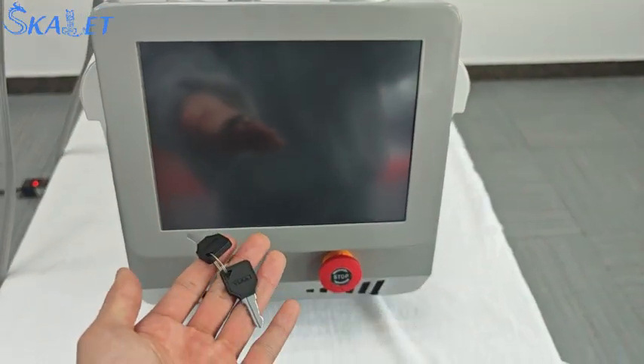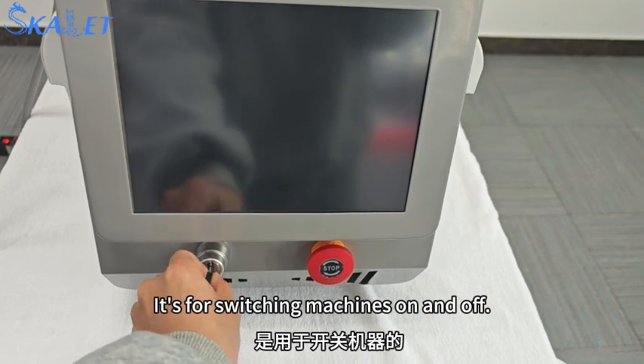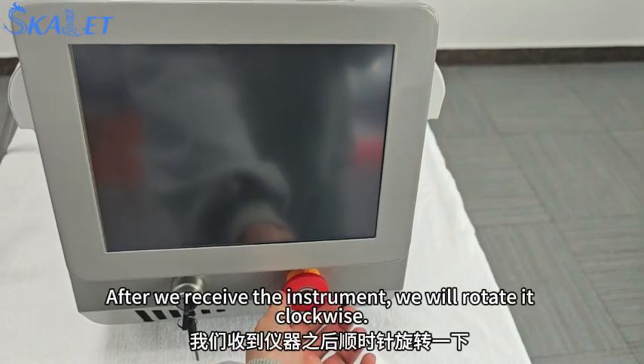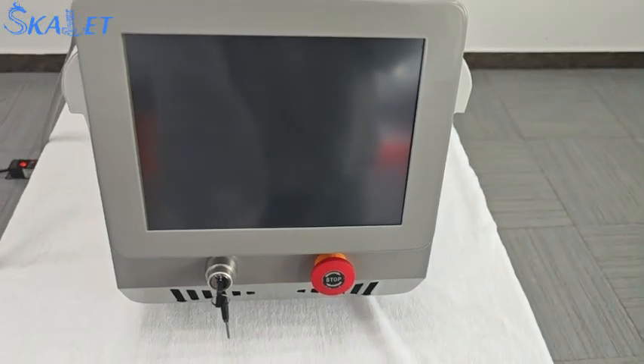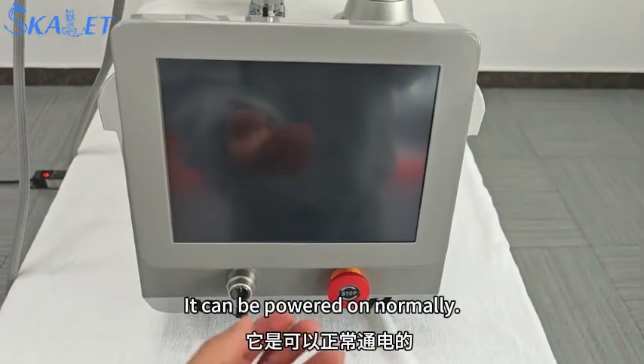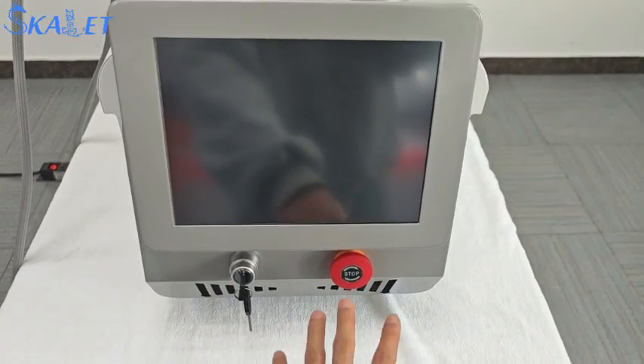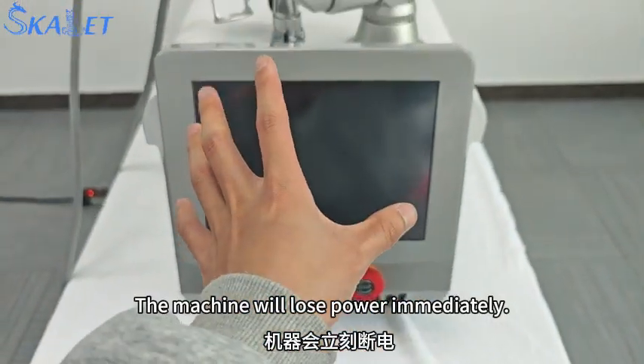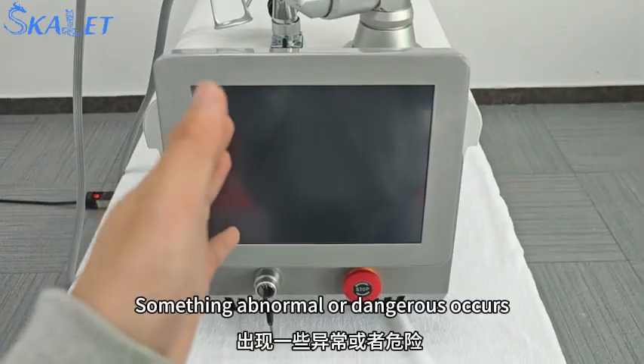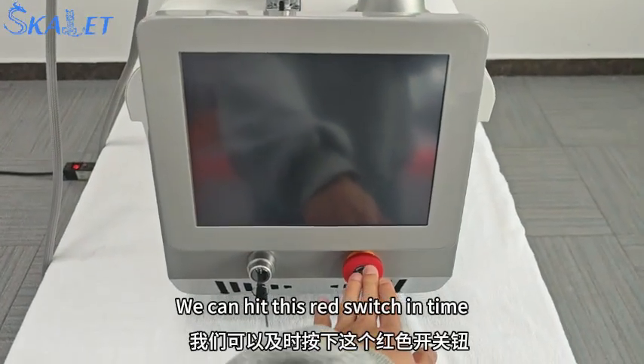Plug the key in front of the instrument. This key comes with 2 in total. It's for switching the machine on and off. This is the red emergency switch. After we receive the instrument, we will rotate it clockwise. If this switch is turned off, it can be powered on normally. When pressed, the machine will lose power immediately. Its function is to prevent use of the machine when something abnormal or dangerous occurs. We can hit this red switch in time and quickly power off the machine.